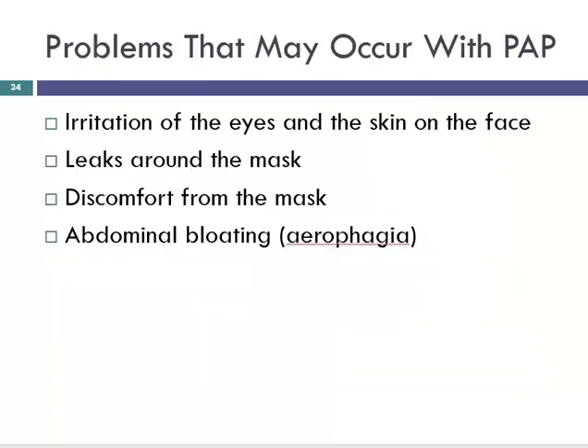Other issues, we can get skin irritation, especially if the patient isn't cleaning the machine or the mask properly. If the mask isn't fitting them well, it can cause irritation, and especially if the air is going into their eyes, it can cause eye issues, conjunctivitis, things like that. A common issue too is swallowing the air, so it can cause abdominal bloating, aerophagia. With aerophagia, or the swallowing of the air, basically when a patient passes gas in the morning, it goes away, but it can be that really uncomfortable gas bubble that they get. So it is something that we take seriously for the patients. I'm not just going to be like, oh, fart it out, you're fine. Usually we'll just turn the machine down a little bit to try to lessen how much air they're swallowing.